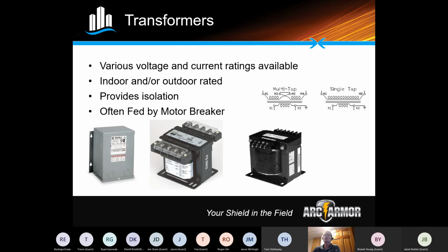Typically, these smaller ones that are shown here on my screen are located within lift station type control panels. It's there to take either 240 or 480 volt power and drop it down to 120 so that we can provide our control power within the panel. In a typical lift station panel, if you have a receptacle that you're plugging in for either powering up a computer or a tool of some sort, these will typically be in the 2 to 5 kVA range.